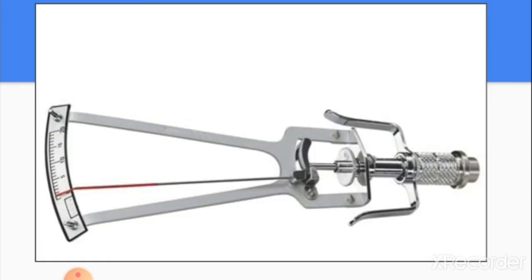The Schiotz tonometer has several parts: a scale, a needle, a lever arm, a plunger, a holder, a barrel, and a footplate. The footplate rests on the cornea, a known weight is placed on the tonometer, and the needle moves along the scale. The distance the needle travels is used to calculate the IOP.